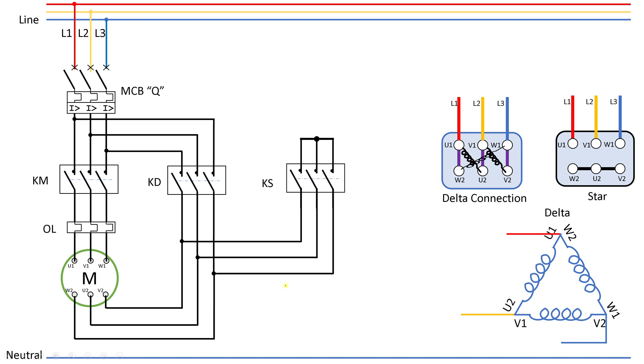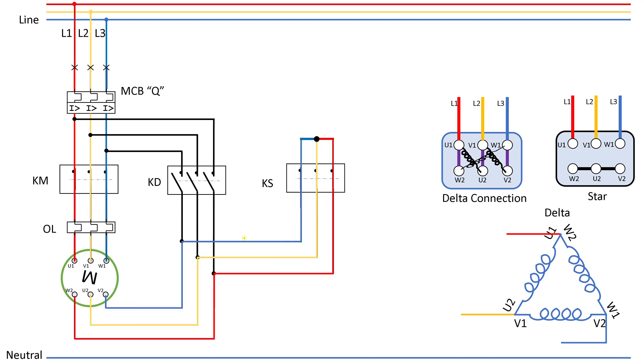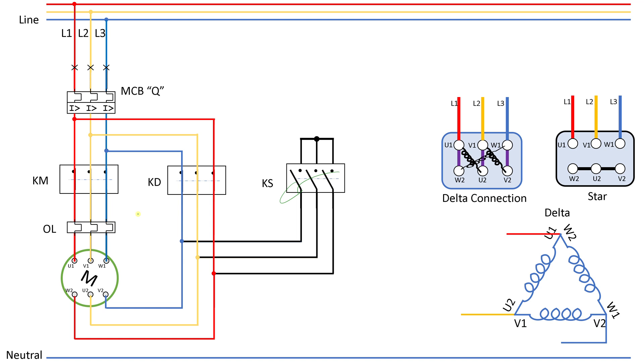Let's see it in action. I'll run the circuit — it will run in star for some time and then shift to delta. I close the MCB, then close the main contactor and star contactor at the same time. The motor is now running in star. After some time, the star contactor opens and the motor is running in delta, where it will continue running until we switch it off.